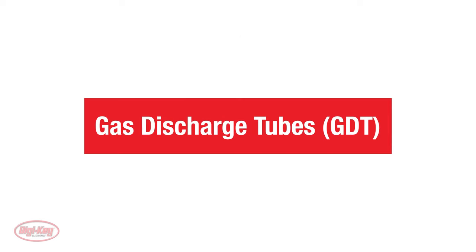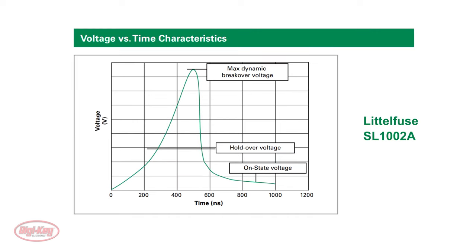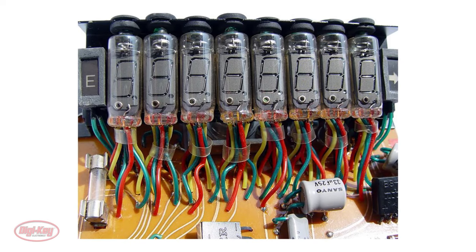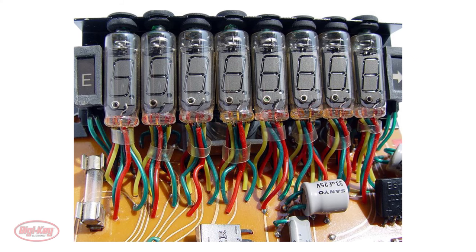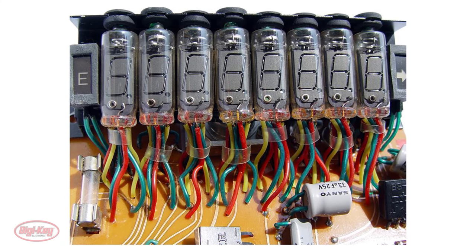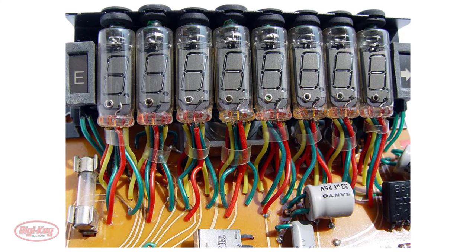Gas discharge tubes, or GDTs, are another type of transient suppressor. GDTs are tubes filled with an inert gas that ionizes at a specified voltage, forming a short to ground. In that regard, GDTs are similar to MOVs and TVS diodes, but GDTs generally have a higher surge current capability, up to 100 kA. The physical nature of GDTs also means they tend to clamp or fire slower and are commonly used with other protection devices.